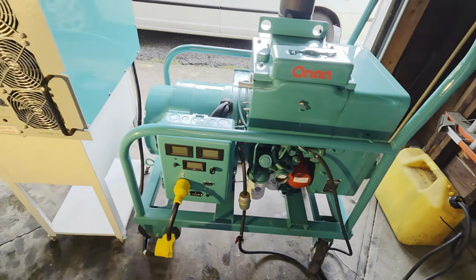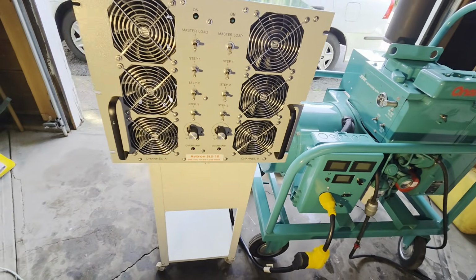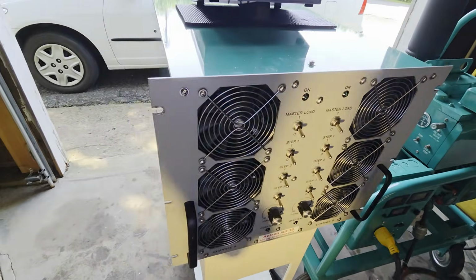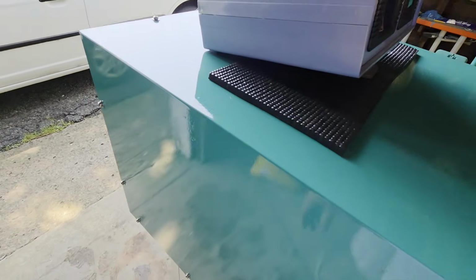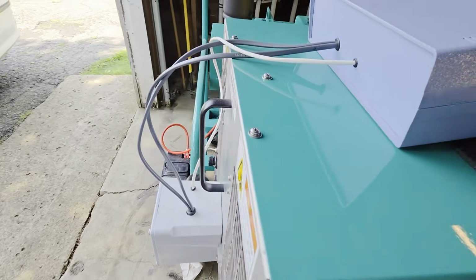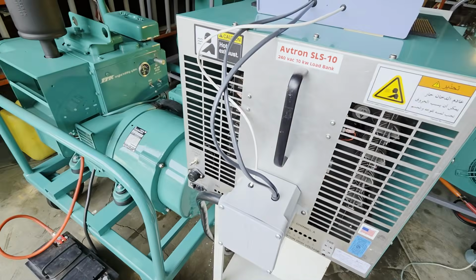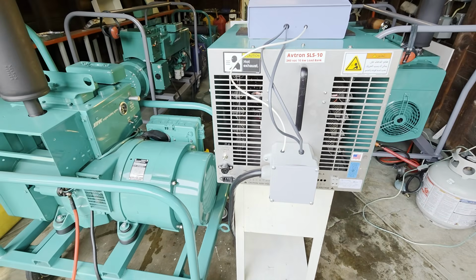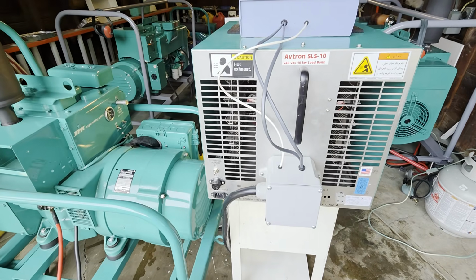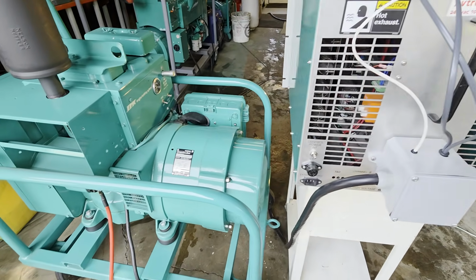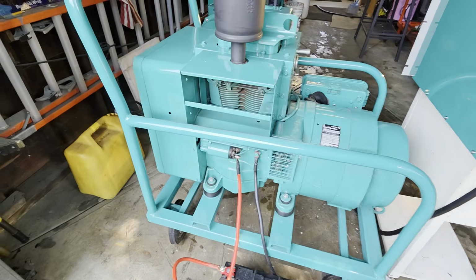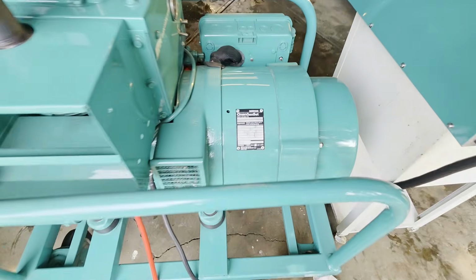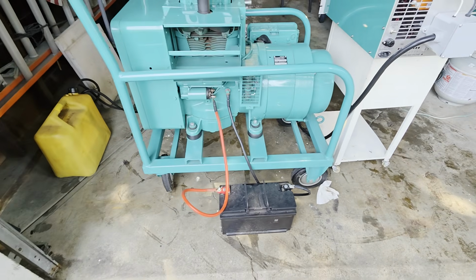Let's take a quick walk around before I start this thing, since you won't be able to hear it once it's running. By the way, this load bank is rated up to 10 kilowatts, but we had about 11.5 kilowatts on it, so it's actually very good. Looking at the rear end here, this is what we've got, nothing special. Here's the data tag for the generator end, a 12 kilowatt YD generator end.